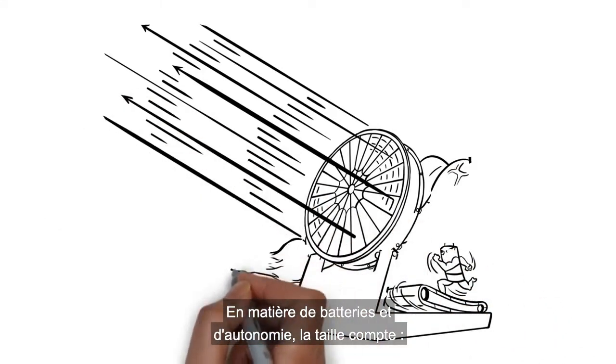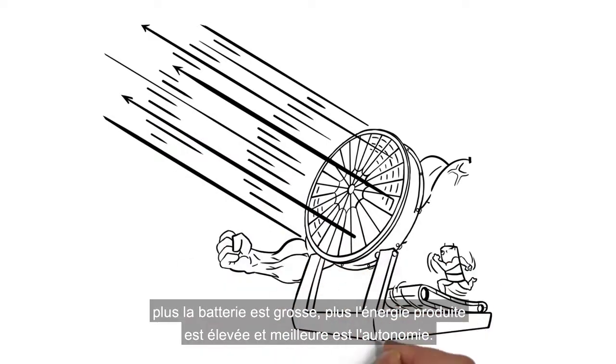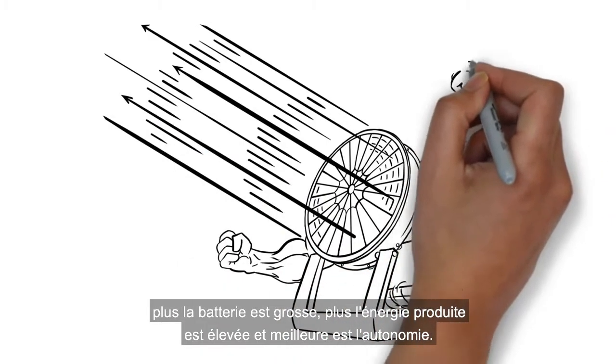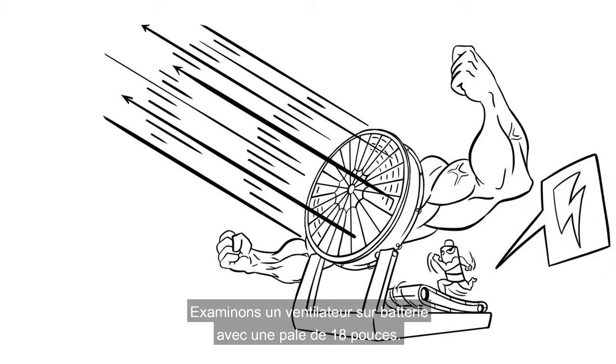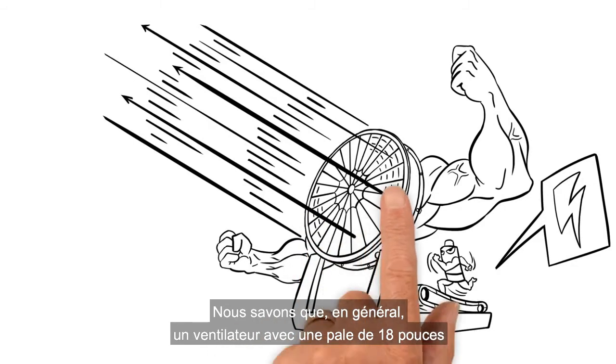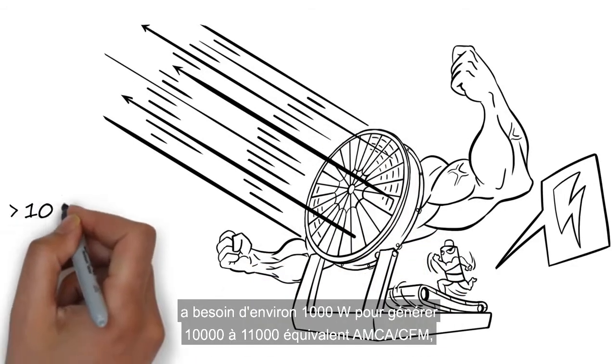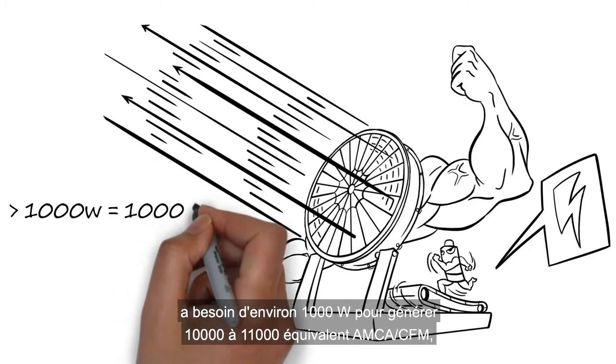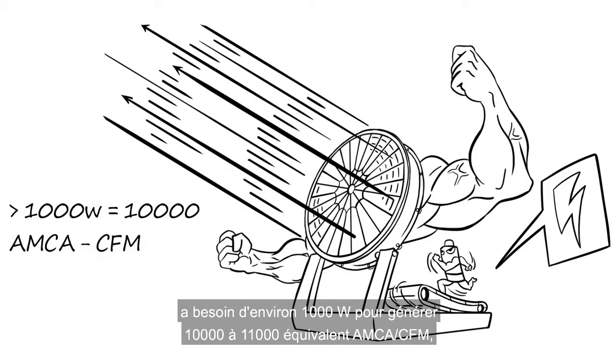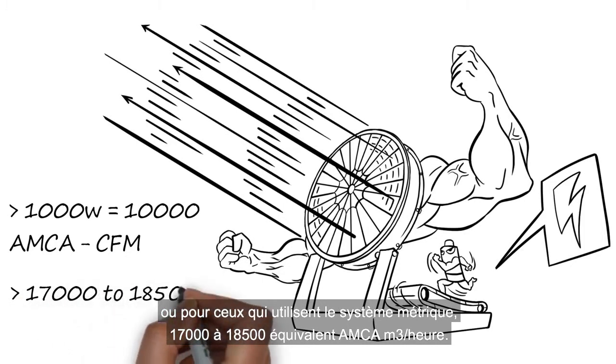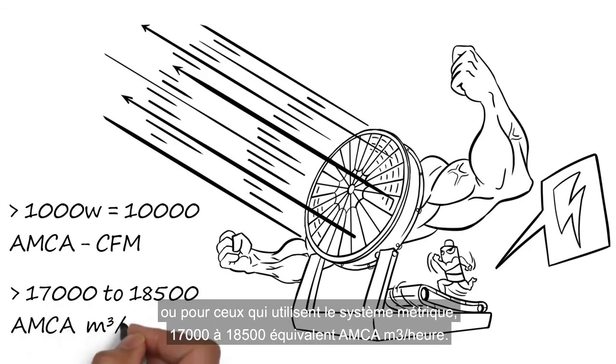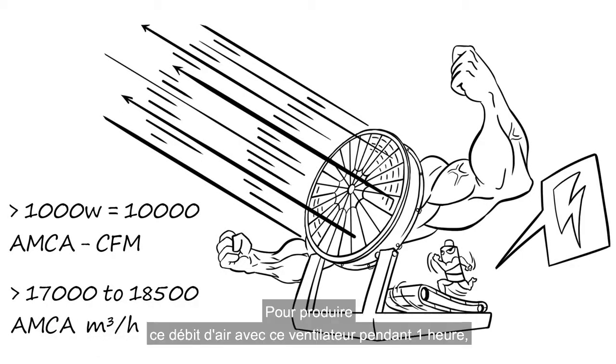Size matters. The bigger the battery, the higher the watt-hour, the longer the runtime. Let's evaluate a battery-driven fan with an 18-inch blade. We know that in general, a fan with an 18-inch blade would require about 1,000 watts to generate 10,000 to 11,000 AMCA equivalent cubic feet per minute, or for those using the metric system, 17,000 to 18,500 AMCA equivalent meters cube per hour.